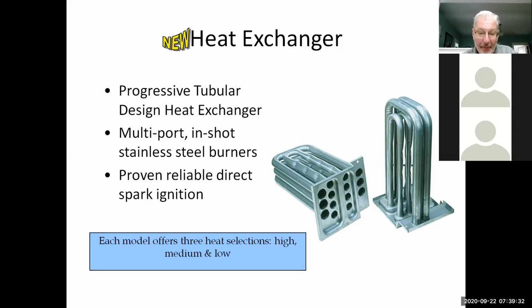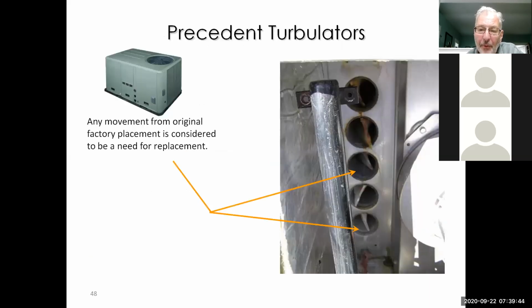So again, if you're putting a heat exchanger in there, make sure you get the low, medium, or high heat exchanger, and that's all designated in the model number. Now the other thing you remember on these units is there are turbulators on most units. Some of the newer stuff, they're changing the design a little bit. They're putting crimps in the heat exchanger. So I think at some point you'll probably see these turbulators disappear.